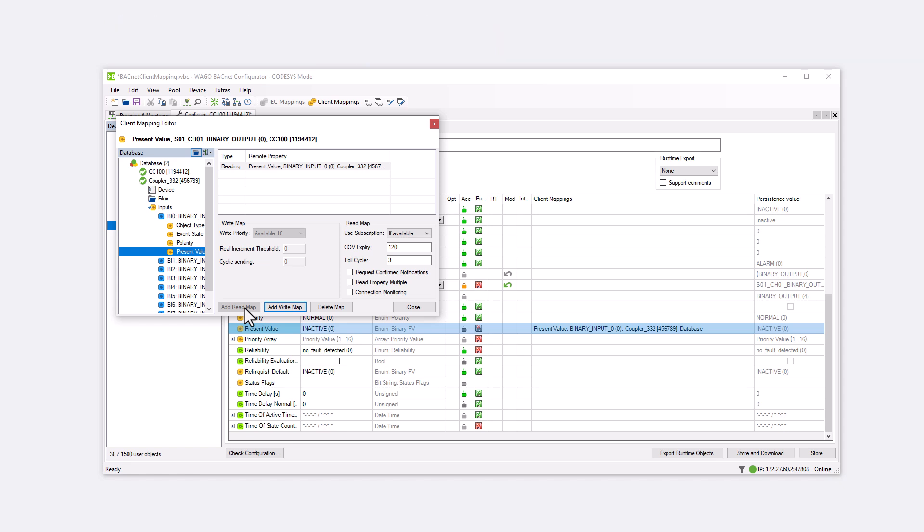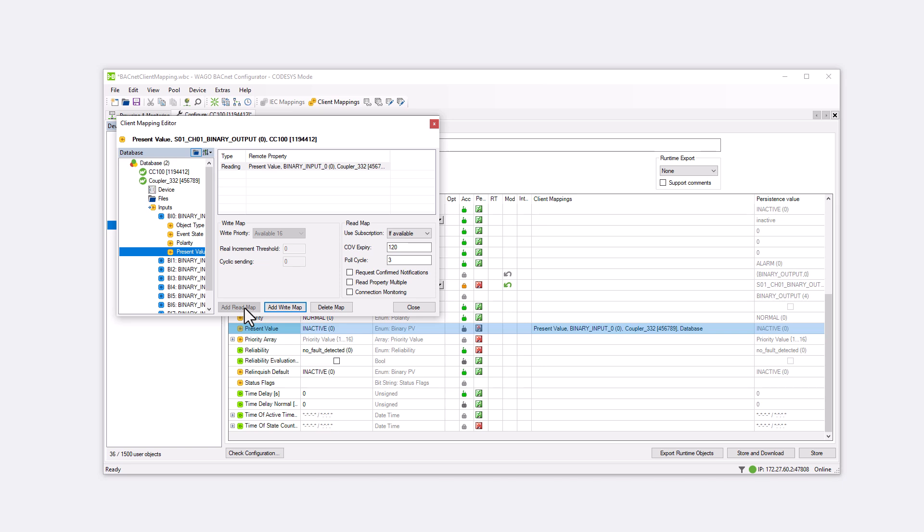The other method is Polling, where the client cyclically queries the current value of the input. The cycle time is preset to three seconds. The longer the cycle time, the less data traffic on the bus. In a BACnet network with hundreds of devices, each with multiple objects polling various properties, a three-second cycle can quickly overload the bus. Therefore, the COV method is preferred.